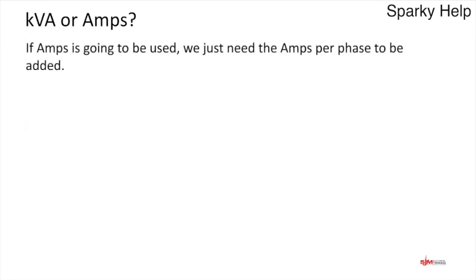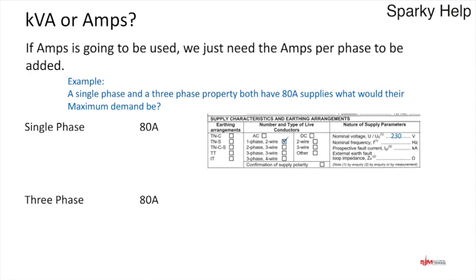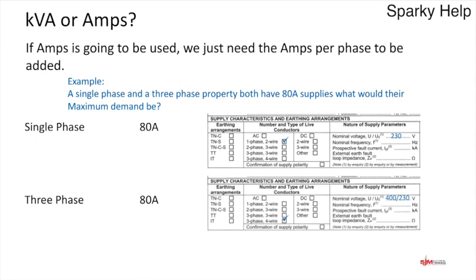What about expressing maximum demand in amps? It's the amps per phase that you need to put on — not the total. For a single-phase installation you'd write 80 amps and delete the KVA. For a three-phase installation it's also 80 amps per phase. If you wonder how you'd distinguish between them, supply characteristics indicate whether it's single-phase two wire or three-phase four wire, with the voltages written in — 230V single-phase, or 400/230V three-phase.